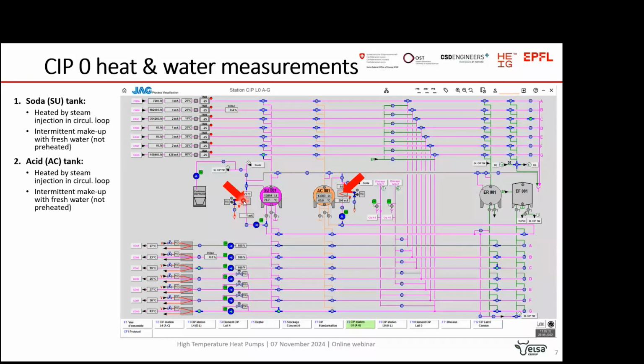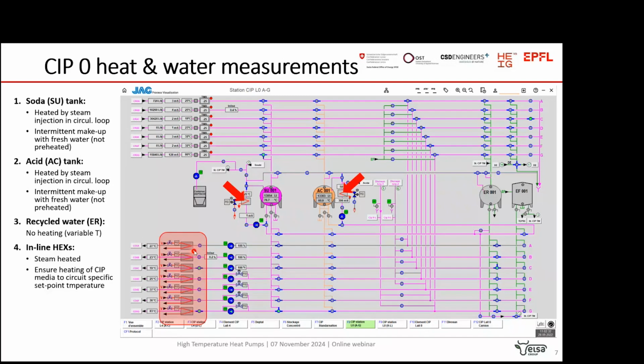To adjust the temperature of the flow to the specific temperature required by the different equipment to be cleaned, recycled water is not heated, and to adjust the temperature for each circuit, we have inline heat exchangers. Here it's not steam injection, but steam heated heat exchanger. For the CIP0, there are 11 circuits.